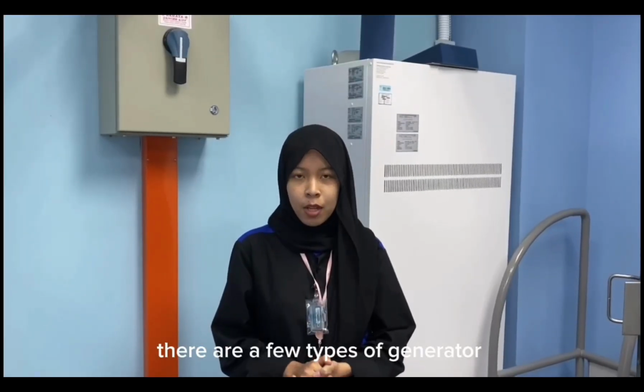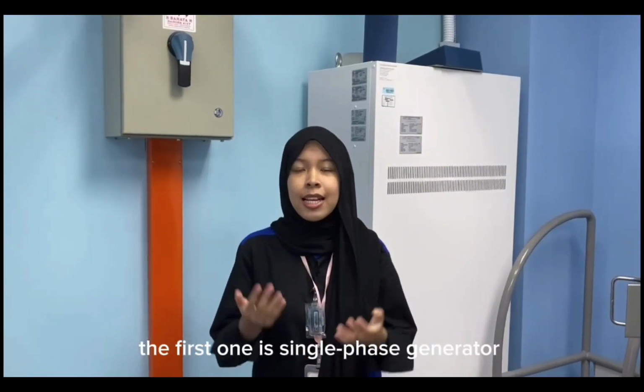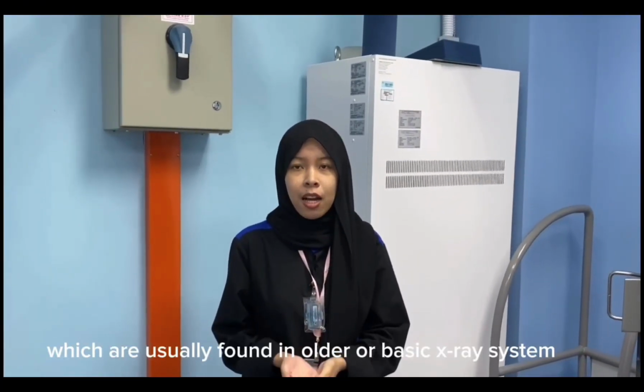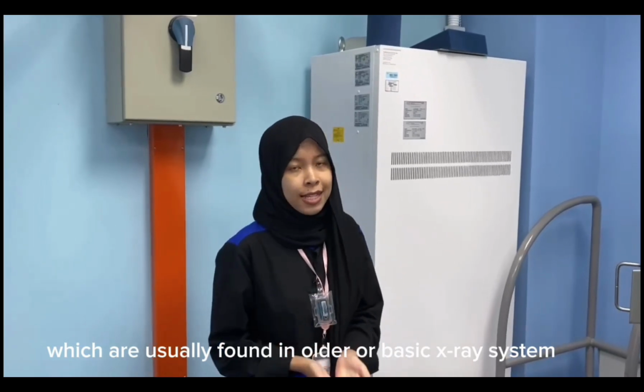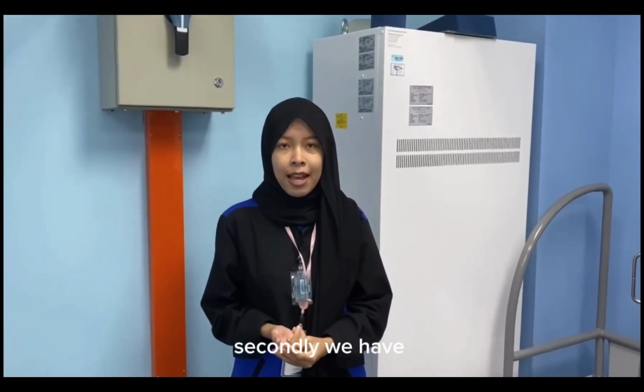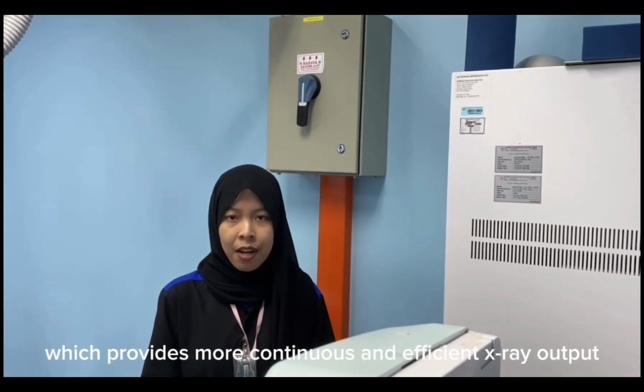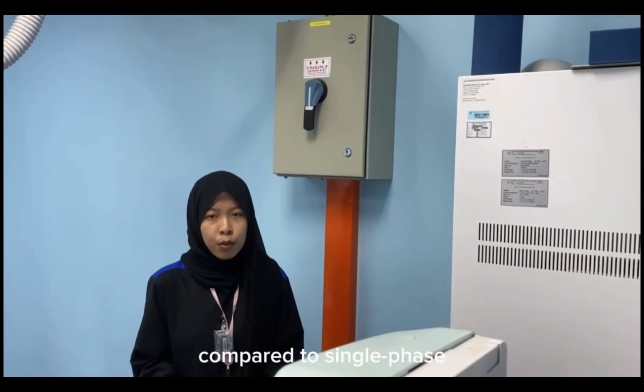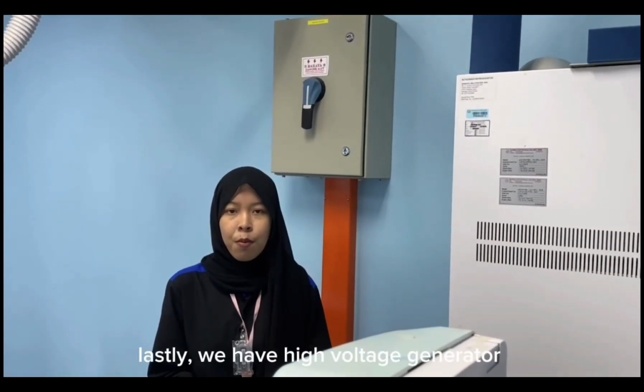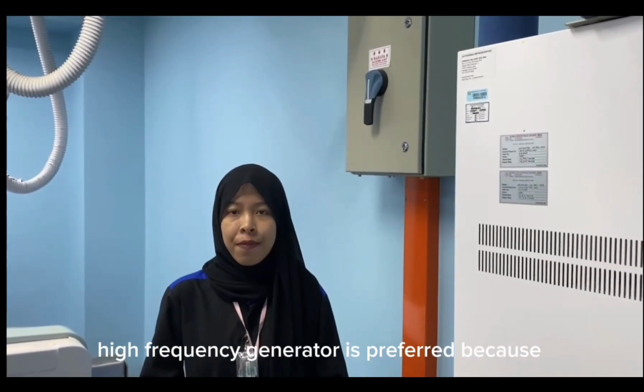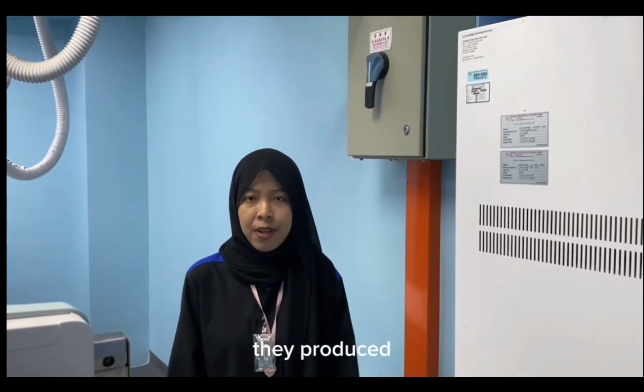There are a few types of generator. The first one is the single-phase generator, which is usually found in older or basic X-ray systems. Secondly, we have the three-phase generator, which provides more continuous and efficient X-ray output compared to single-phase. Lastly, we have the high-frequency generator, which is most commonly used in modern X-ray machines.